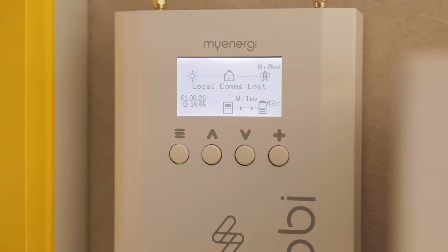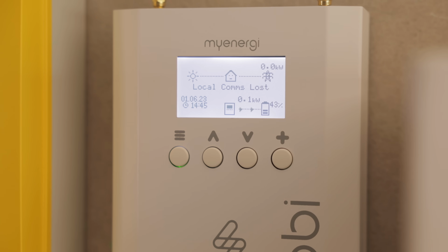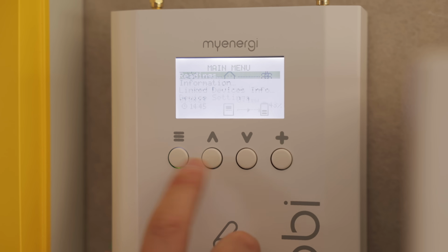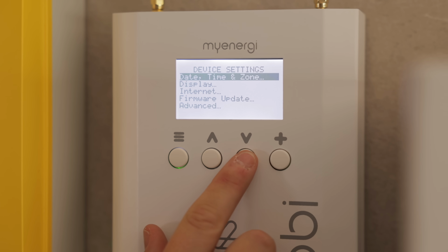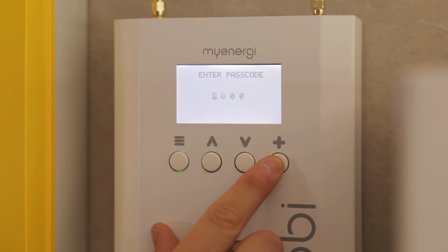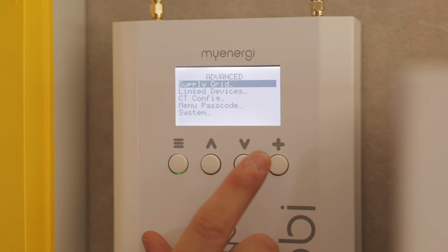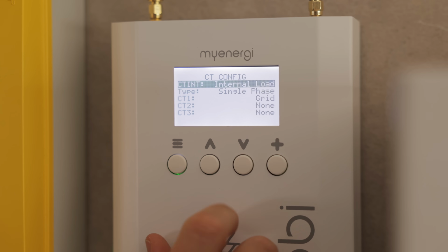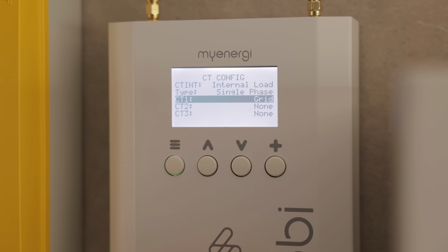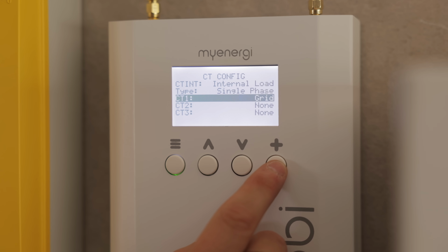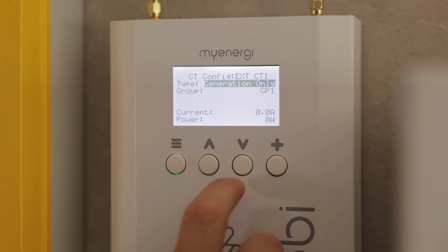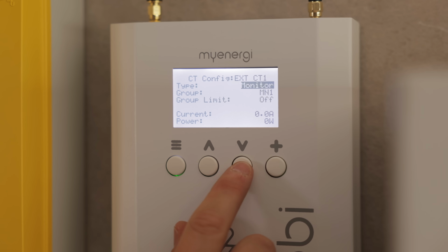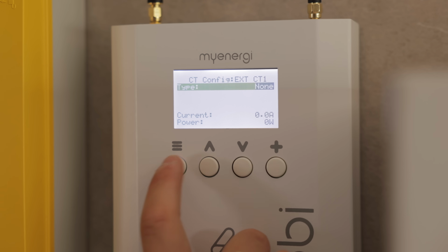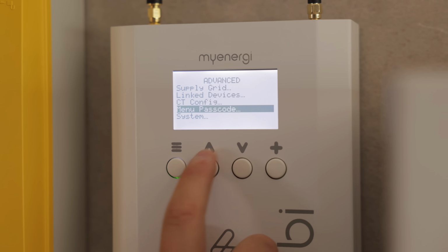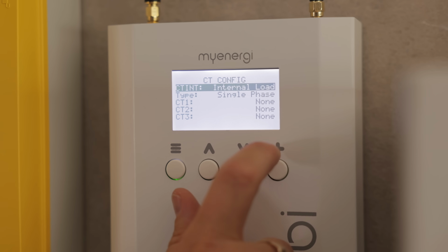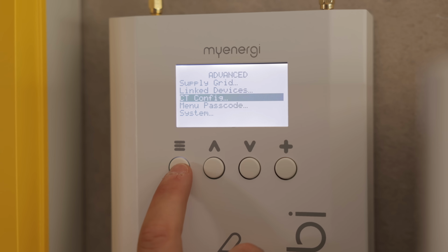Okay, so now that the initial configuration is done, we need to do the CT configuration. To do that, we go into Menu, Device Settings, and then Advanced. The enter passcode for advanced is always 000, and then CT config. Now CT1 is always set to grid, but as we've already got a grid CT connected to the Zappi, we're going to turn that off in this particular case, so just set it as none. Now CT config shows all of the CTs are set to none, which is correct.